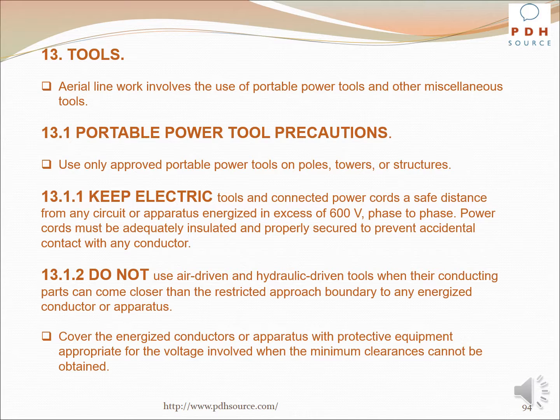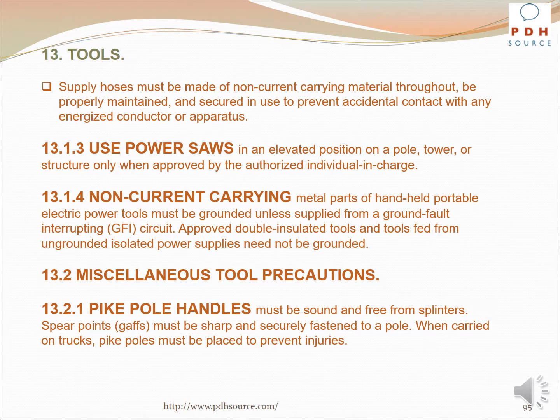Do not use air-driven and hydraulic-driven tools when their conducting parts can come closer than the restricted approach boundary to any energized conductor or apparatus. Cover the energized conductors or apparatus with protective equipment appropriate for the voltage involved when the minimum clearances cannot be obtained. Supply hoses must be made of non-current carrying material throughout, be properly maintained and secured in use to prevent accidental contact with any energized conductor or apparatus.